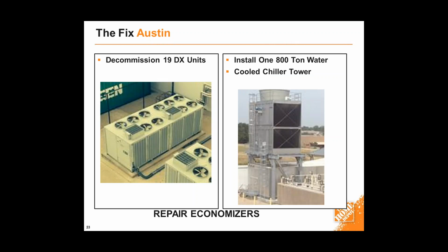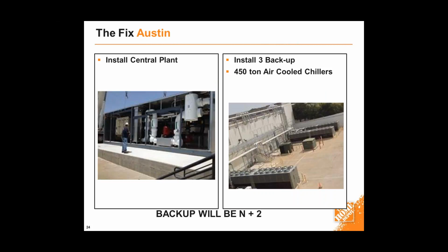In Austin, we decommissioned 19 DX units and installed one 800-ton water-chilled tower. We repaired the economizer, and for the units feeding all the floor areas we changed out the motors from 50 horsepower to 35 horsepower with VFDs, reducing energy significantly. We also installed a central plant with three backup 450-ton air-cooled chillers, so now our backup is N+2 and it's not such an emergency anymore.